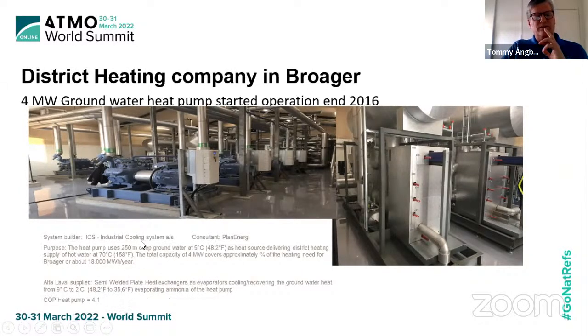So the COP of the heat pump was 4.1. So here we had a little higher. I would say today most heat pumps try to achieve a COP of 4 or more, and with the help of our heat exchangers, this can be raised in the future even further, we hope.